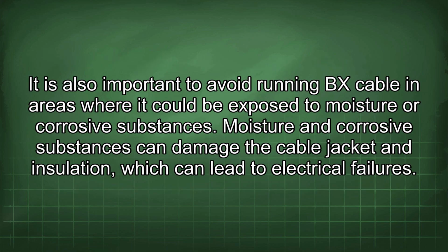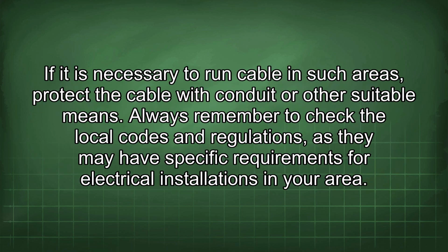It is also important to avoid running BX cable in areas where it could be exposed to moisture or corrosive substances. Moisture and corrosive substances can damage the cable jacket and insulation, which can lead to electrical failures. If it is necessary to run cable in such areas, protect the cable with conduit or other suitable means.